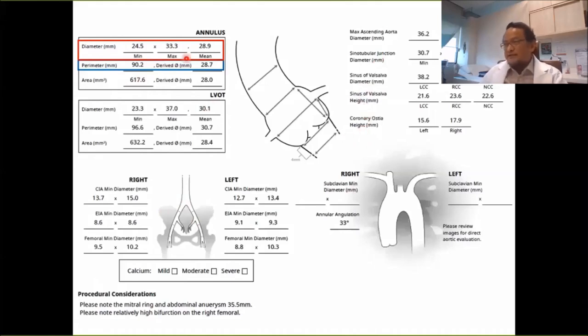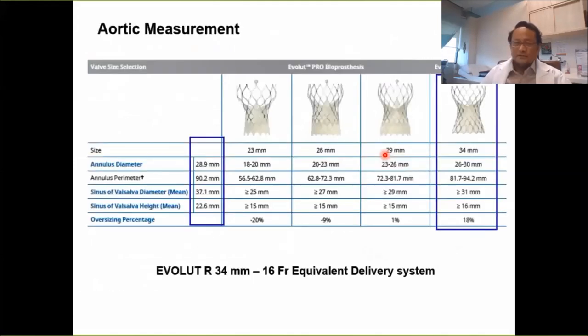So in this case, this is a large perimeter and requires a large valve. And if you look at the valve that has been chosen, which is a 34 mm Evolut R valve, these are the parameters that we assess and see whether the patient's own measurements comply with this. So this is what we term as ideal if all these parameters are met.